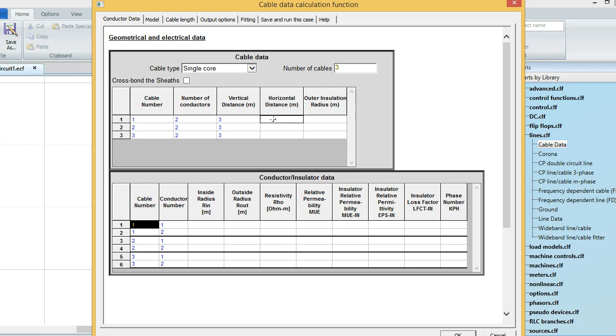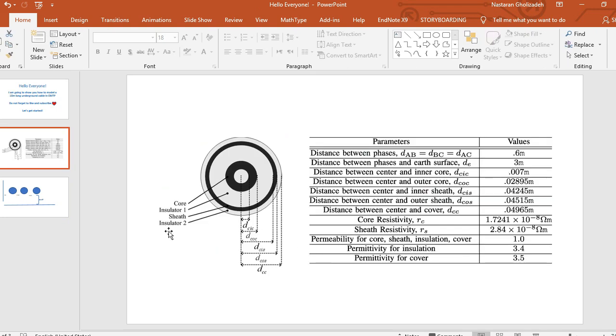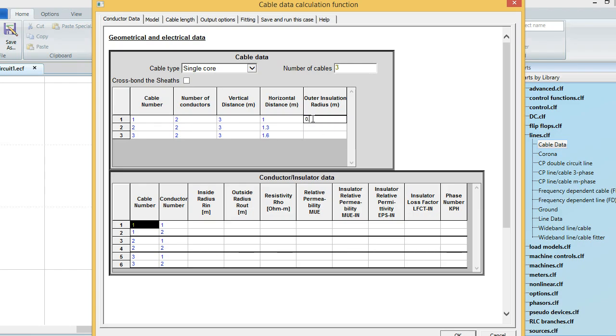The entries are 1, 1.3, and 1.6 meters. What is the outer insulation radius? Outer insulation is Insulator 2 and the radius is dcc. The value for dcc is 0.04965 meters. I'm going to enter this data for all phases since I assume all cables are identical.